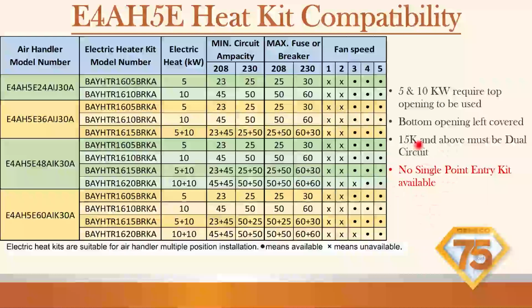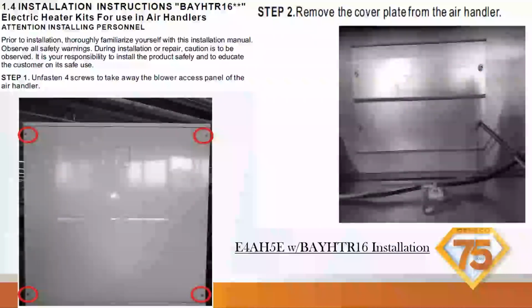This is important. No single point entry kit is available for this air handler. So there's no single point entry kit where we have one massive sized wire to supply the 20 kW and 2 60 amp circuits, right? Single point entry kits are where you've got one heavy sized wire and you're splitting it into 2 different circuits, because that single wire feed from the panel would supply 120 amps possibly. There's our 2 plates. So we've got an upper and a bottom. So keep that in mind. We've got 2 plates.